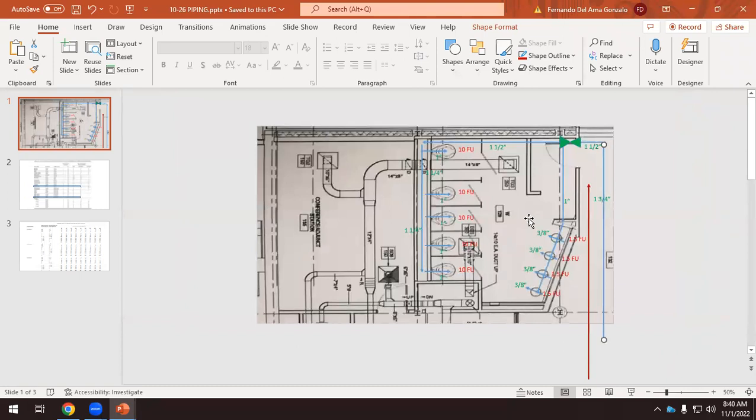Now, the big question, what is the length? Usually for this, it's better, and in Revit we do have the drawing. But here we'll say, if this is the cold water supply, this is the city supply. Where's the distance between the city to the entrance of the building? I don't know. It can be 5 feet or 1 foot or whatever. And then there will be a vertical pipe going up. We have two floors, so this is 50 and 50, or around 30.